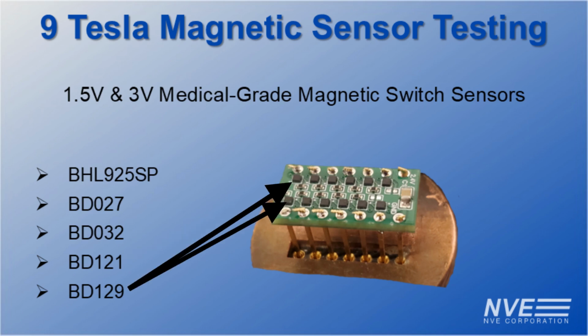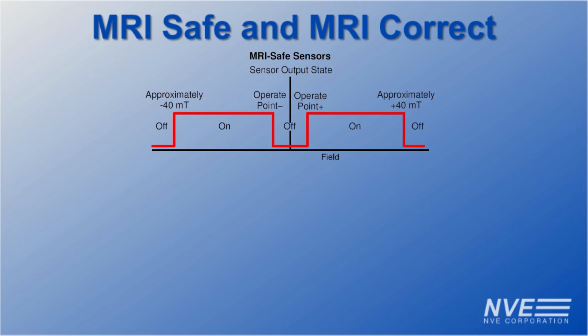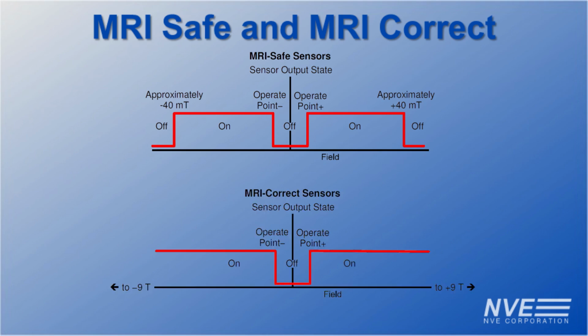and the BD129. All NVE medical-grade sensors are MRI-safe, meaning they cannot be damaged by magnetic fields up to 9 Tesla. However, some sensors cannot maintain the correct output state at high field strengths, beginning usually at 40 millitesla or 400 Gauss. Sensors that are designed to maintain the correct output at large fields are MRI-correct, in addition to being MRI-safe. This is what we are testing for.